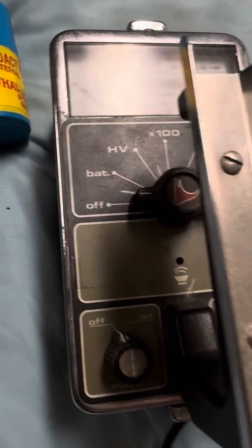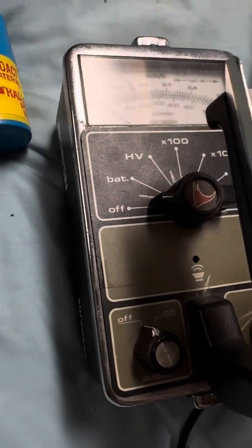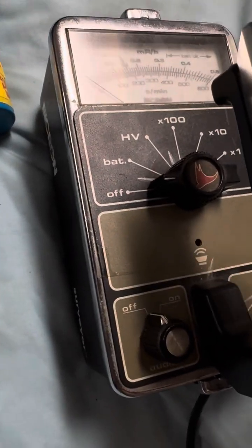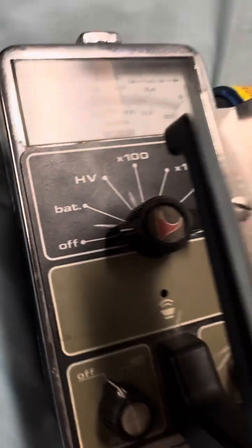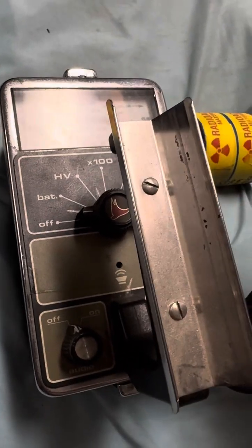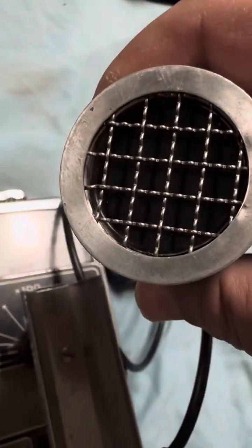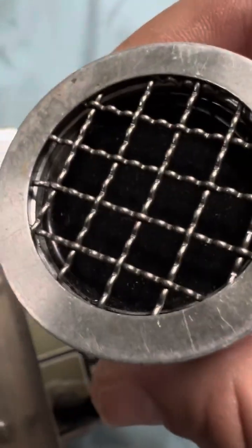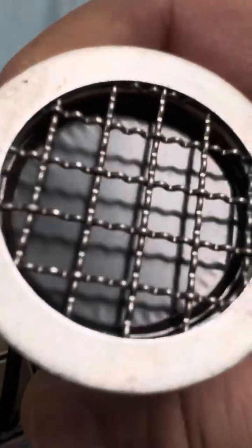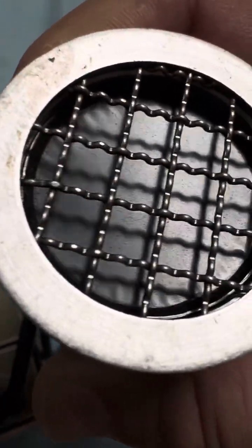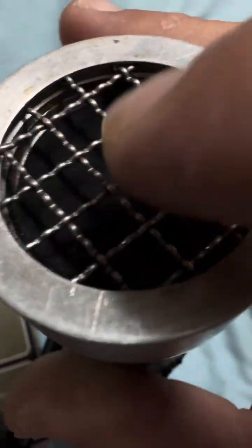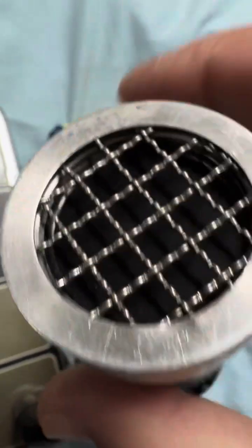This one comes with a special probe. These are normally paired with HP-270 gamma beta only probes. But this one in particular is the HP-190, which detects alpha radiation in addition to beta and gamma. What you're seeing right now is the thin window on the probe that's made of mica and is very fragile, so it's protected by a mesh screen.